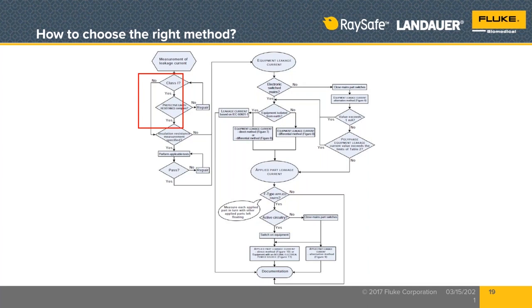So if the device that we're testing is not a class 1 — now class 1 typically means that there are three connections on the power cord: L1, which is our hot wire, L2, which should be our neutral wire, and some means of ground. In the United States, we have 3 prongs on the plug end. In Europe, the EU power plug for 240 volts AC doesn't have a third prong for the ground, but it has a ground connection that makes connection with another metal piece on the mains power.